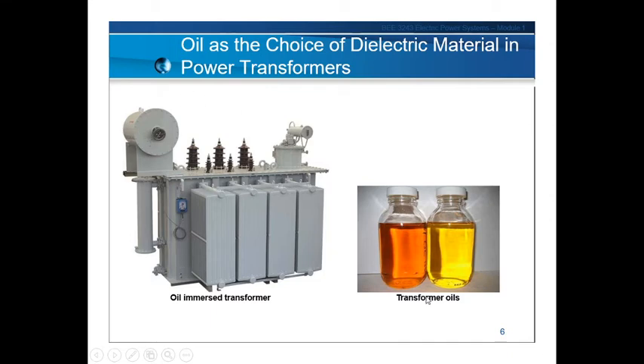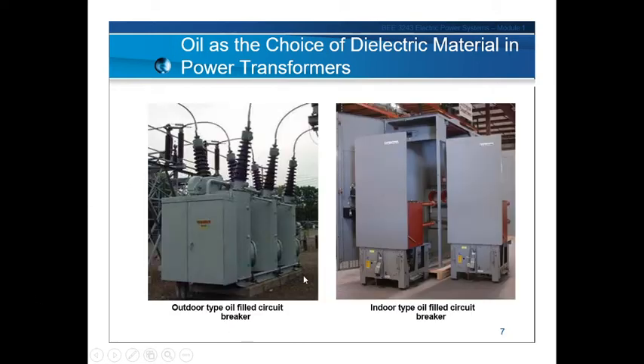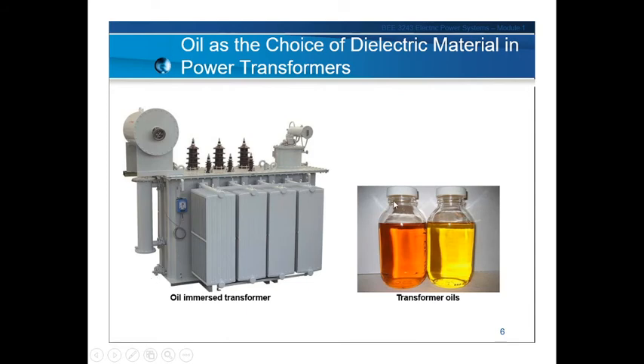Most of the time, engineers check the breakdown capacity of the transformer oil, so they take samples from this portion. They take the oil samples and run the breakdown test subject to the potential the transformer is subjected to. Let's say when it is 33 kV, they take a sample and go to the lab and subject a voltage exceeding 33 kV to find out whether the liquid still maintains its breakdown voltage.